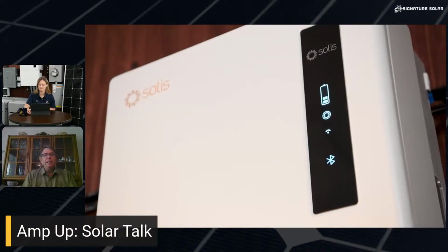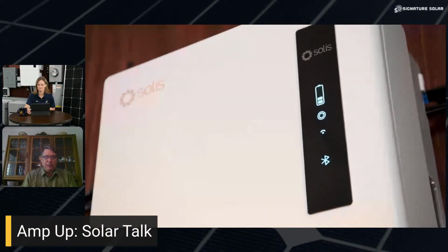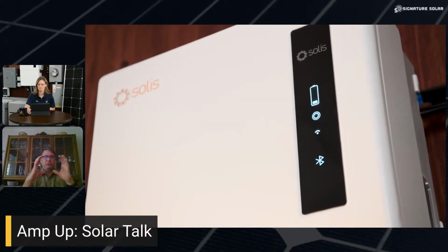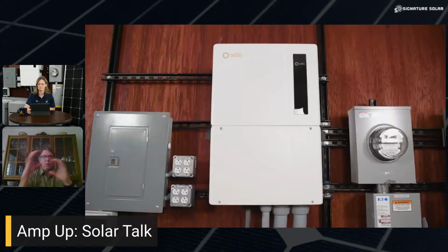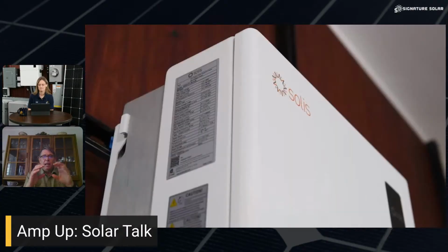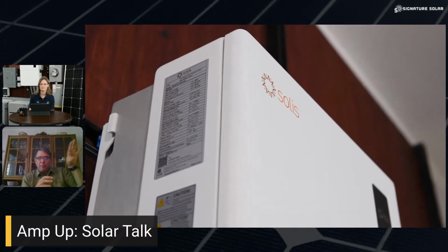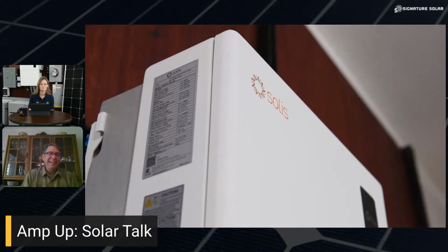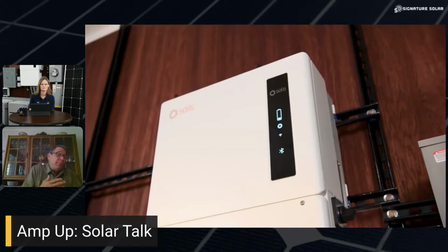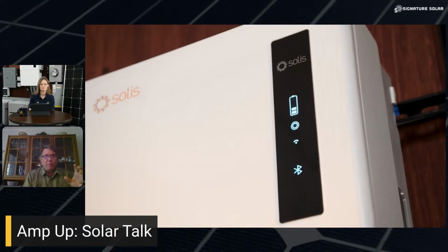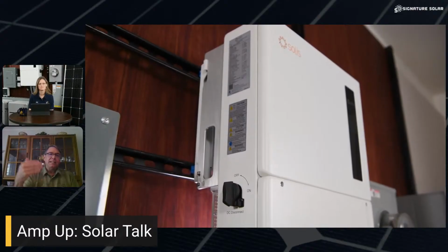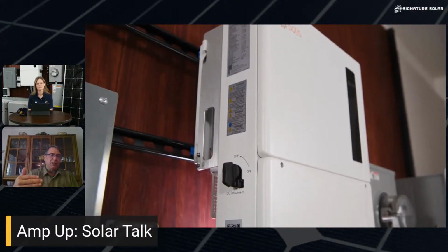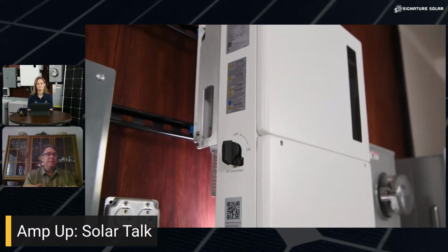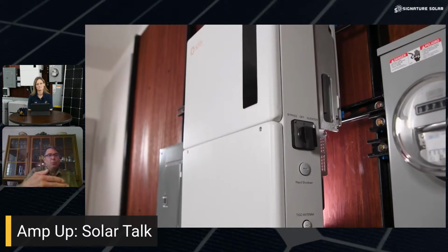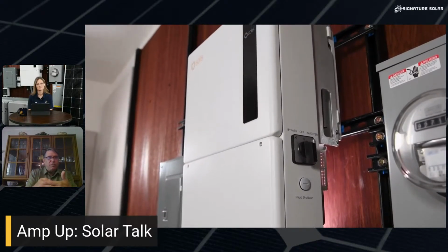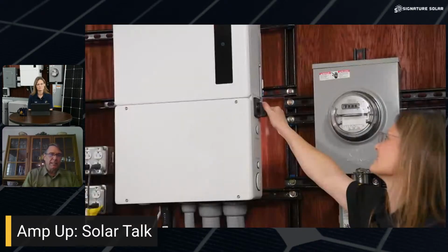There's really nothing that you couldn't change. The inverter is kind of like the electron traffic cop of the whole system—it's the brains. The PV on the rooftop, you could change or add more PV to bring in. For the batteries, let's say you had a Solis S6 with one LG battery and wanted to add another—you can parallel that LG to the first LG and connect them both to the Solis S6.